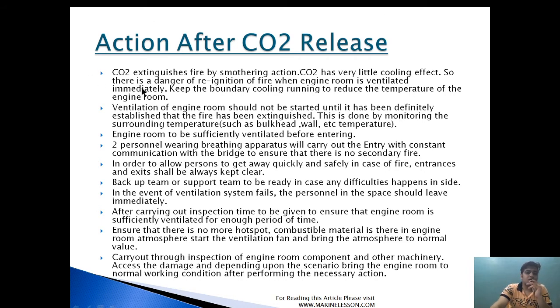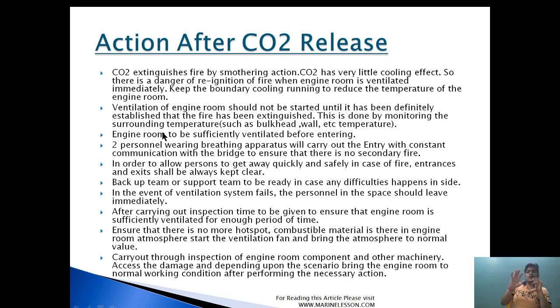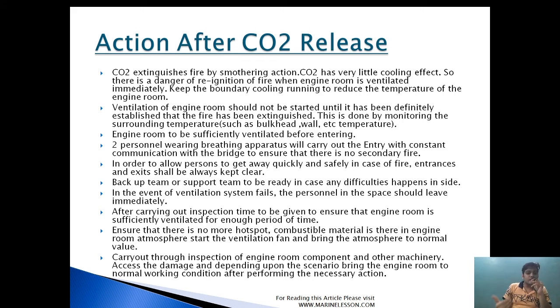CO2 extinguishes fire by smothering action but has very little cooling effect, so there is a danger of re-ignition when the engine room is ventilated immediately. Therefore, boundary cooling is used to reduce the engine room temperature and avoid re-ignition. Ventilation of the engine room must not be started until it is confirmed that the fire is extinguished — otherwise admission of air will aggravate the fire. Surrounding temperatures are monitored; when boundary temperature falls from around 80°C down to 20–25°C, the next step can proceed.